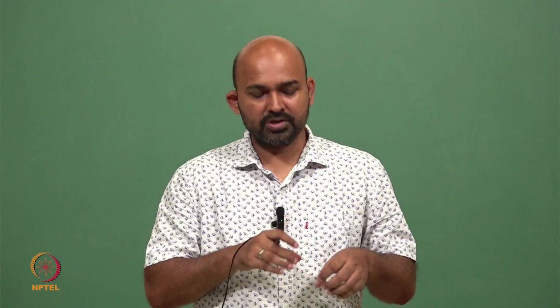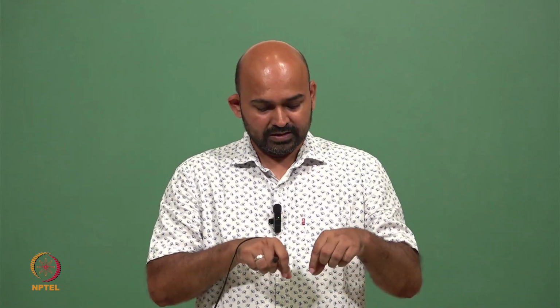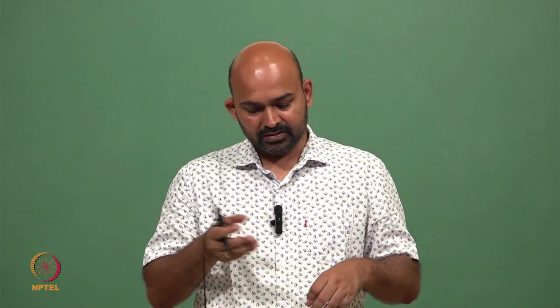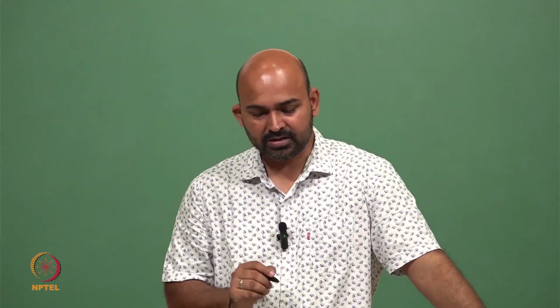and that is also proportional to the number of gamma ray photons we detected, because the material is generating a proportional number of photons from these gamma ray photons. So this is the typical structure of a scintillator.